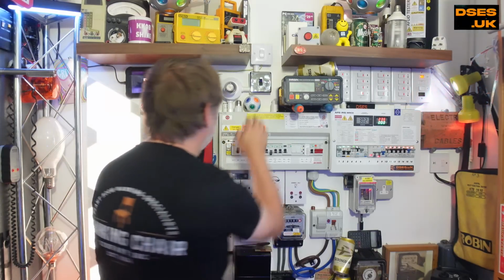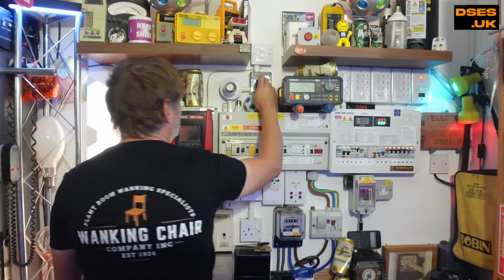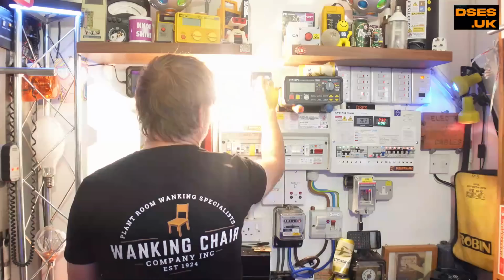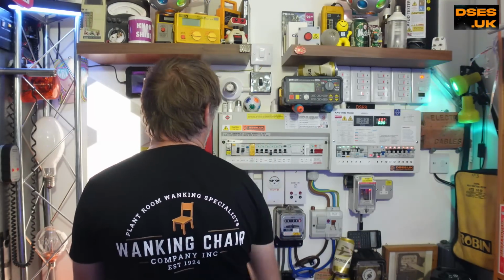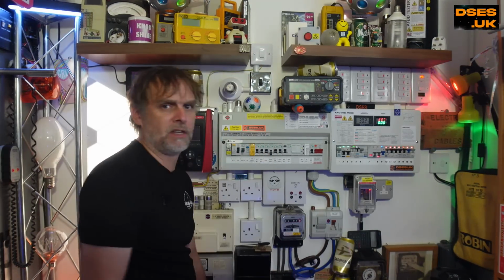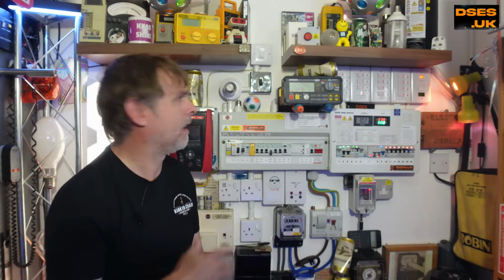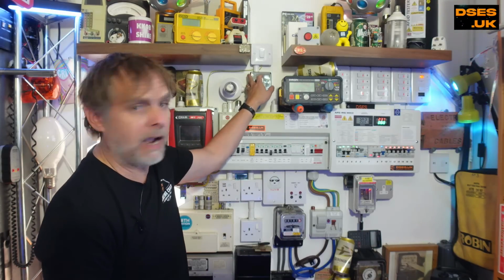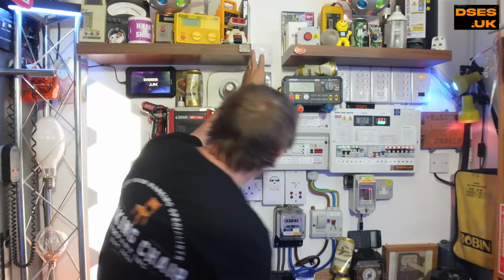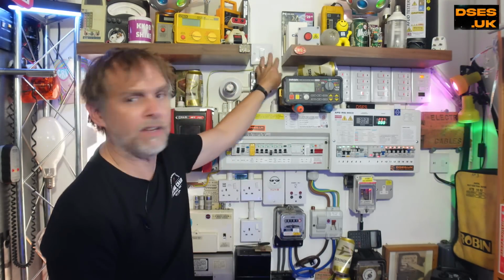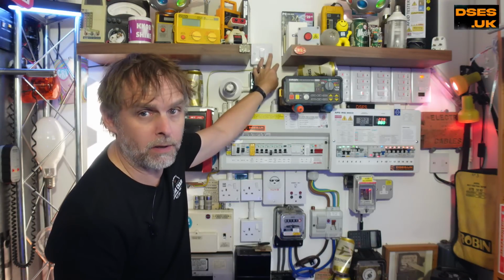Like James, I have two light switches here. I suspect James served two different lighting points; mine serve the same lighting point, but it doesn't really matter for demonstrating this fault, it'll all be the same. The metal switch has a protective conductor attached, and the plastic switch sits atop a metal knockout box, which also has a protective conductor attached. Hence, this metalwork and these faceplate screws ought to be earthed.